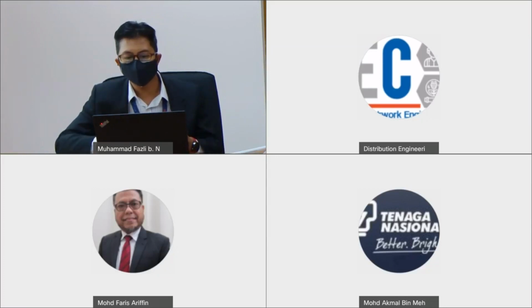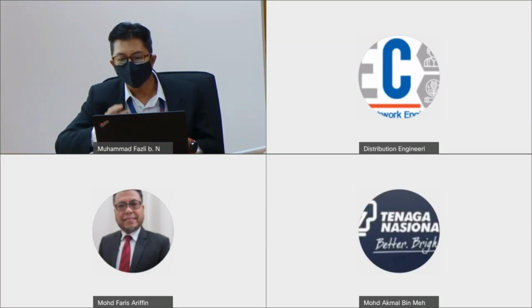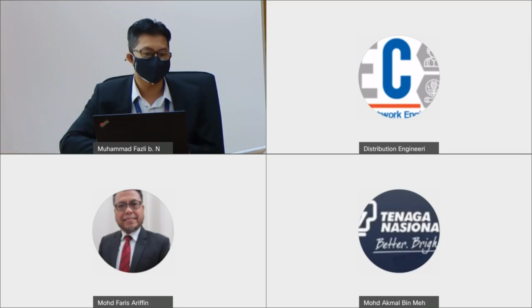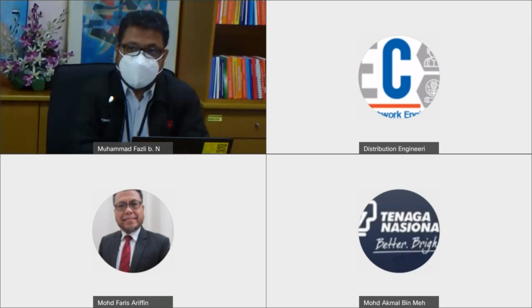Sir, how about areas prone to lightning? What are the best methods to prevent lightning interruptions? For those areas having a high density of lightning activities, I think the best way is we can use the IEEE 1410 recommendation, where we can install surge arresters at every 1 or 2 spans. But we have to make sure also that the soil resistivity or the pole footing resistance is meeting the minimum requirement. But if we have a system with high lightning activities, but with poor soil resistivity or pole footing resistance, we can mitigate or even minimize the effect of lightning current with the use of LLPD, or the line lightning protection device. I hope that answers your question.